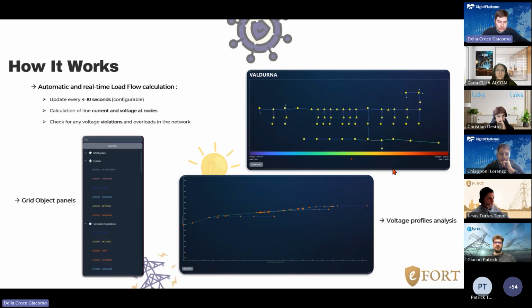Then we have real-time operation, another fundamental component of the smart grid controller that allows load flow calculation in real time. The system updates this calculation every 4 to 7 seconds, depending on the configuration, and calculates with mathematical methods parameters like line currents, node voltages, voltage violations, and eventual network overloads.